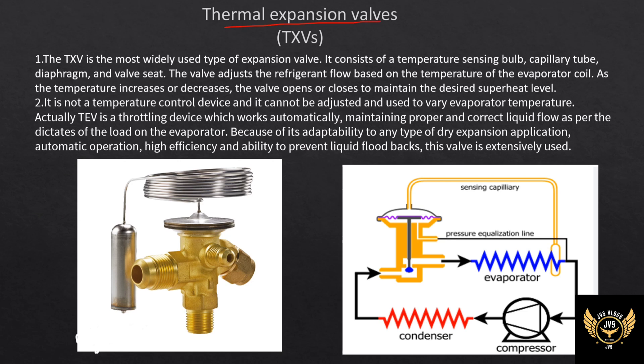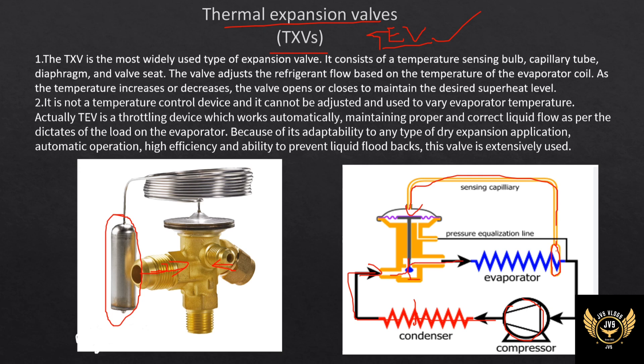First, the thermal expansion valve — it is called TEV or TXV. This is a temperature-based system. In the VCR system, after the compressor, condenser, and expansion valve, the thermal expansion valve uses a sensing bulb placed at the outlet of the evaporator. It senses the temperature and operates the valve to supply the required amount of refrigerant to the evaporator.